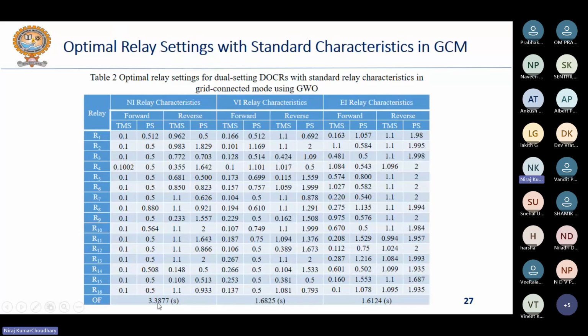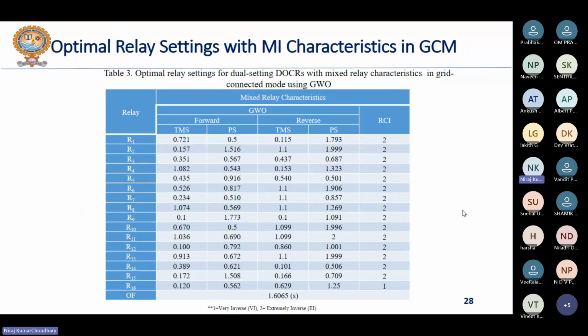There is a huge reduction in the total time of operation of the relay, as we have changed the relay characteristics from normal inverse to very inverse. And again, when replaced the relays with EI, extremely inverse characteristics, then there is further reduction in the total time of operation of the relay, right? This is justified, as you have seen in the IDMT characteristics, that for a similar fault current level or plug setting multiplier level, the time of operation for the relays with extremely inverse characteristics was least.